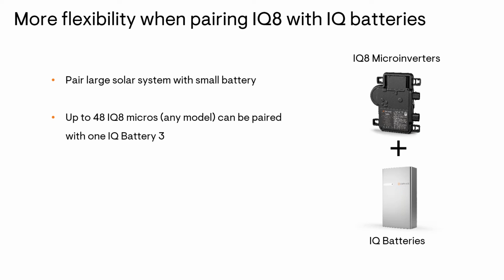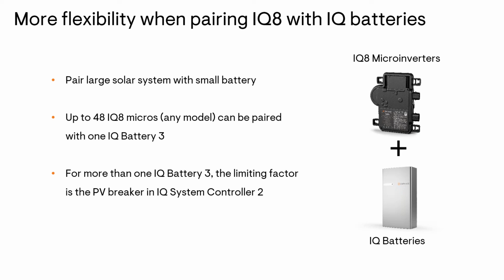Now, if more than one IQ battery 3 is being installed, which is nearly always going to be the case, then the limiting factor is actually in the IQ system controller. The PV breaker rating at a maximum is 80 amps, which means that 64 amps of continuous current can feed into the IQ system controller from that breaker. So that would translate to 64 IQ8s, up to 52 IQ8 pluses, 44 IQ8Ms or IQ8As, or up to 40 of the most powerful model we have, the IQ8H.